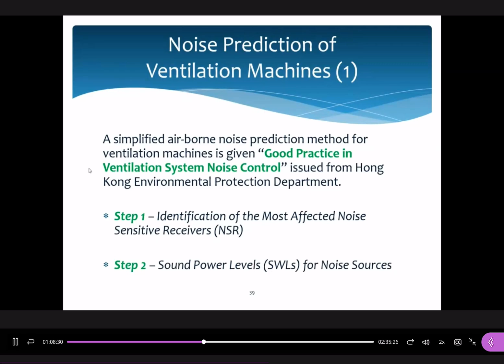The second step is the sound power levels for the noise source. For the sound power levels of different sources, you can refer to this table. The first one is for air cooled chillers, which have different sound power levels under different cooling capacities. We just read these guidelines to do the predictions. The second one is typical sound power levels for water cooling towers, and the last one is typical sound power levels of fans under different pressures, 125 Pascal or 750 Pascal.